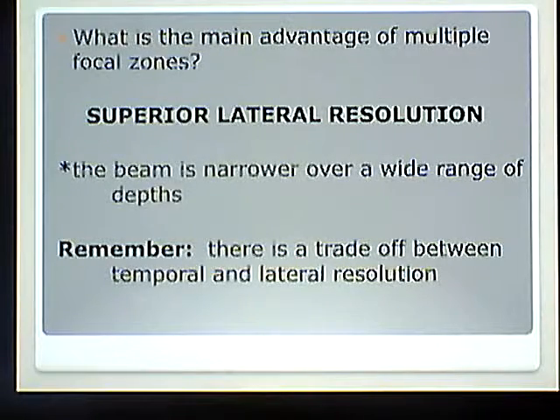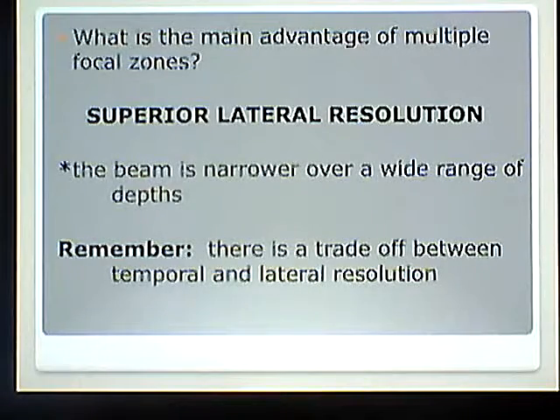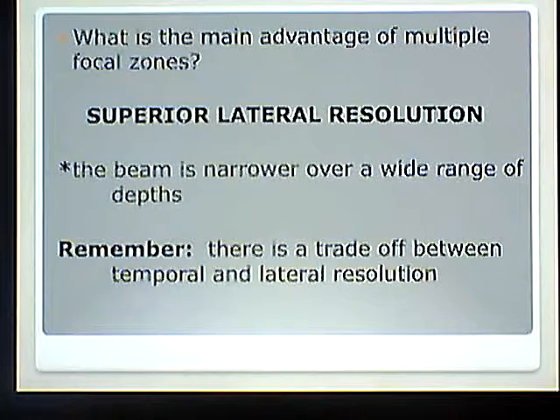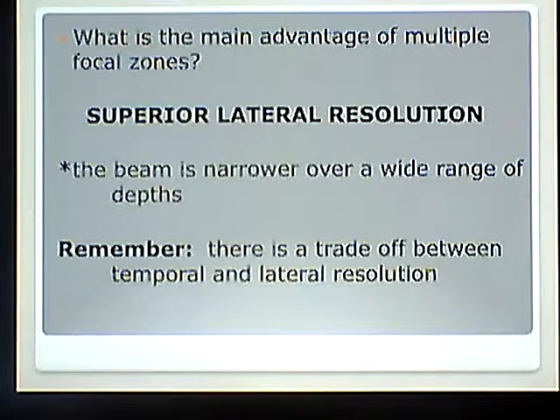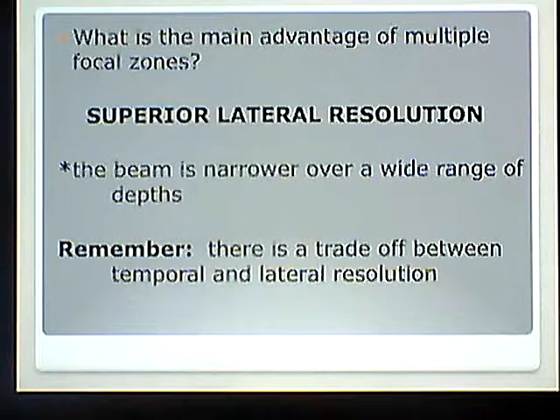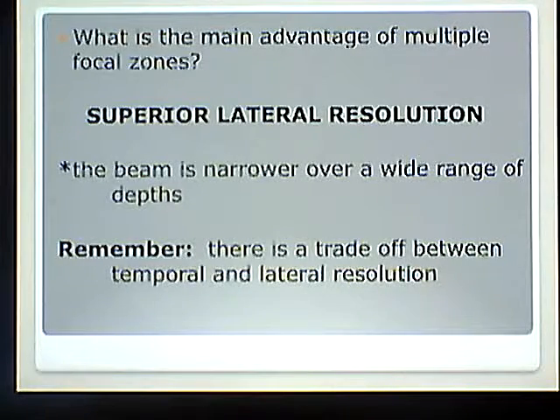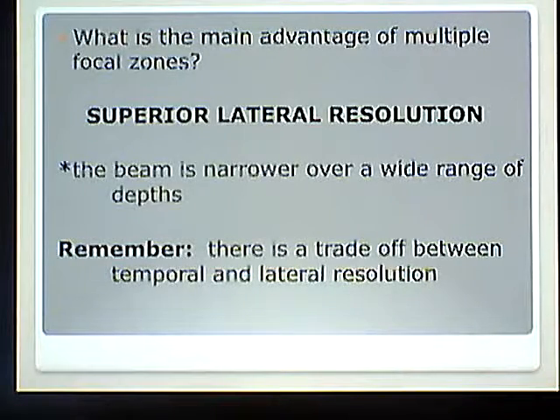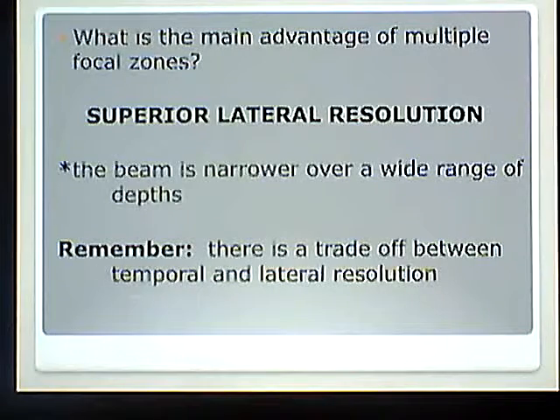The main advantage of multiple focal zones is superior lateral resolution, because we're narrowing the beam at all depths. However, there is a trade-off between temporal and lateral resolution. If I put four, five, or six focuses on that image, I get a beautiful picture but it slows down the moving image. Both can't fully coexist — you have to find that trade-off somewhere in the middle.